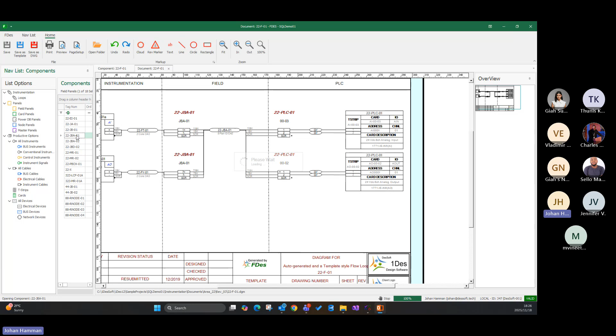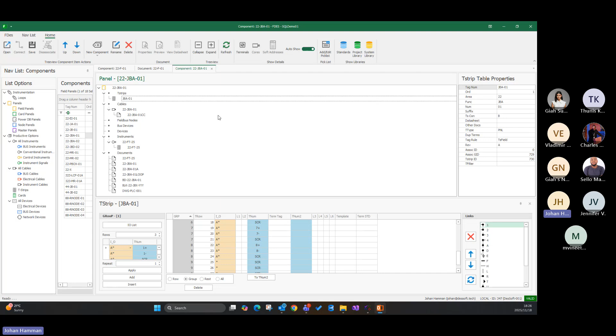If I want to find this field panel, I can go to field panels, which is that JBA one. So there it is. I double click on it, and now I've got my JBA, and I can see the panel details for it. Inside the JBA, there's a T-strip, and I can see there are 24 terminals, from 1+, 1- all the way down to 8+, 8- screen for this JB. Then the cable tells me it's an 8-pair cable, and there it is, 1 white, 1 black, screen, 24 cores all the way to the bottom until we get 8 white, 8 black, screen. That's detailed information.